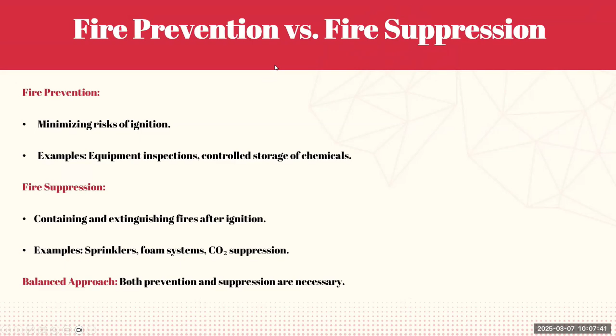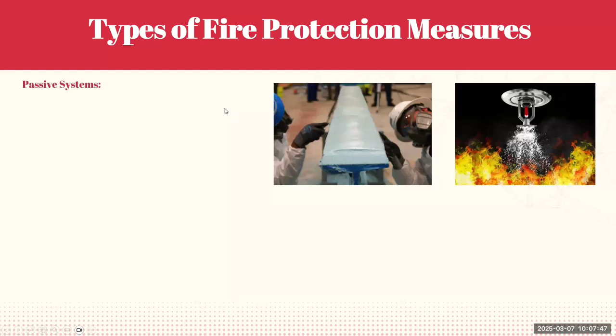All right, now let's talk about types of fire protection measures. So we have passive systems, which include fireproofing coatings, like the one you can see in the image, fire barriers, and compartmentalization. So we ensure that we have barriers so that we don't experience the so-called domino effect, where if one equipment area goes on fire, the fire doesn't spread so easily.